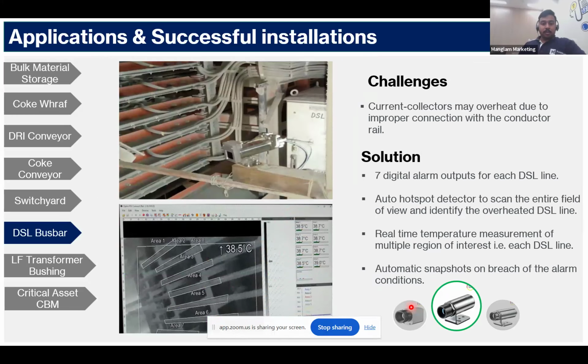For DSL busbar, current collectors may also overheat due to improper connection with conductor rails. Our thermal camera enables real-time temperature monitoring with multiple regions of interest. Out here in the thermal image, you can see we have marked multiple areas of interest, and this triggers when the hotspot exceeds the threshold. We can provide up to 9 AOs and DOs, with an automatic snapshot of the field of view on the breach of temperature conditions.